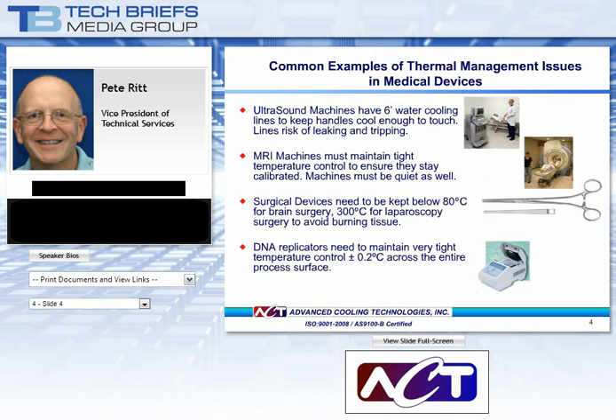There are safety regulations which limit the maximum temperature at which surgical devices can be safely used. We previously mentioned temperature limits for skin contact. Listed here are temperatures for brain surgery and laparoscopy. Maintaining devices below these temperatures can provide for faster treatments, higher throughput, and less downtime. Finally, PCRs, polymerase chain reactors, thermocyclers used in DNA replication, require very good temperature uniformity across the processing area. I listed 0.2 degrees C as the typical uniformity spec, but some are even tighter. These devices also need fast response times, changing temperatures at 2 to 5 degrees per second while maintaining that uniformity. As I mentioned, these are just some applications of thermal management in medical devices. Of course, there are more, and the principles and the technologies that we will be discussing today are applicable to all of these.